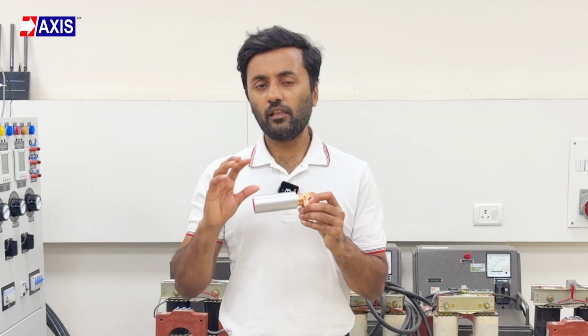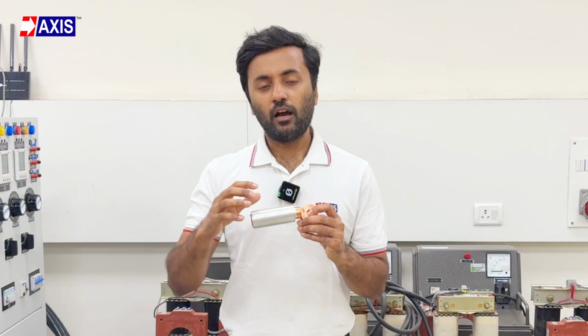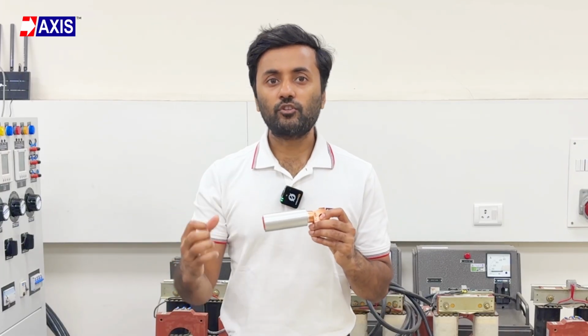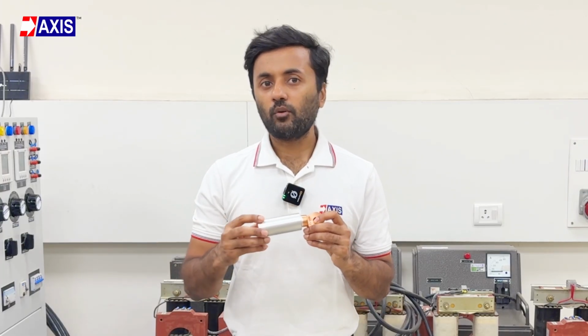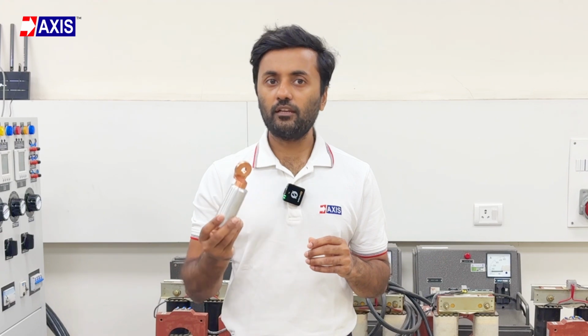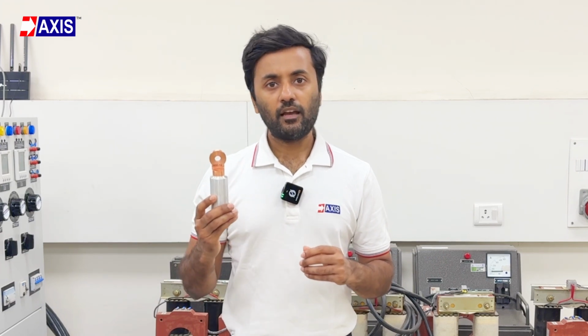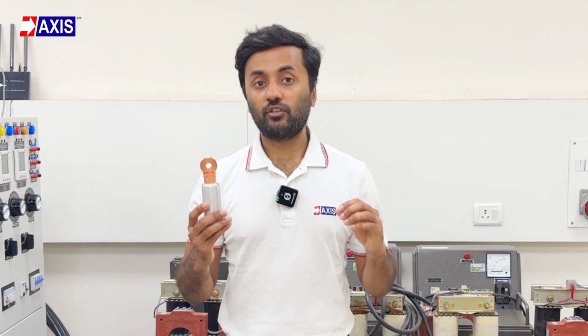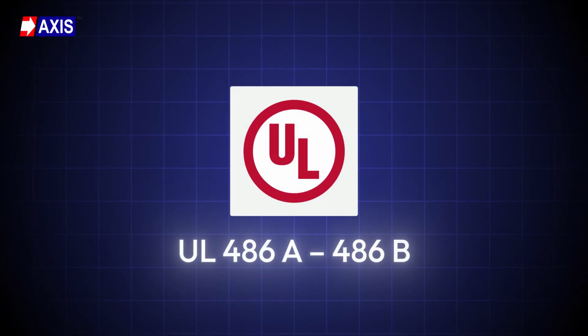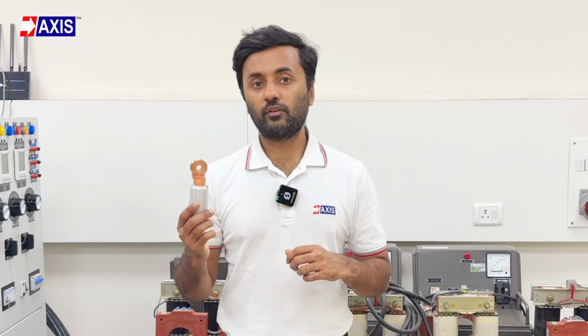It tests how well the lug maintains the electrical connection under mechanical stress, temperature changes, and vibration. It also verifies that the lug does not degrade when subjected to thermal cycling and moisture exposure, ensuring they will perform reliably in harsh environments. This lug should also be tested to UL 486A and UL 486B. This standard ensures wire connectors perform reliably under thermal cycling, electrical stress, mechanical loading, and environmental exposure. These tests verify your lug is safe for electrical installations.